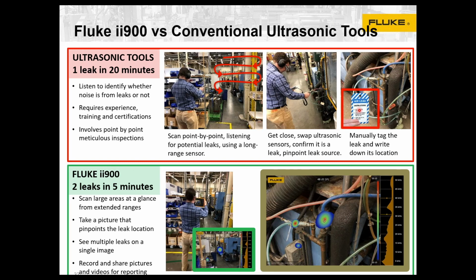And then typically you would tag the leak, write down its location, and then move on. With acoustic imaging, you can start from a great distance away. So if you keep these two terms in mind, detect and locate, that's really the power of acoustic imaging. You can detect at a great distance. So if you see something, you can actually move much closer to it and then pinpoint the actual leak source much more quickly. So rather than taking 10, 20, 30 minutes to track down one leak, you can find multiple leaks in minutes without that training, without that experience.